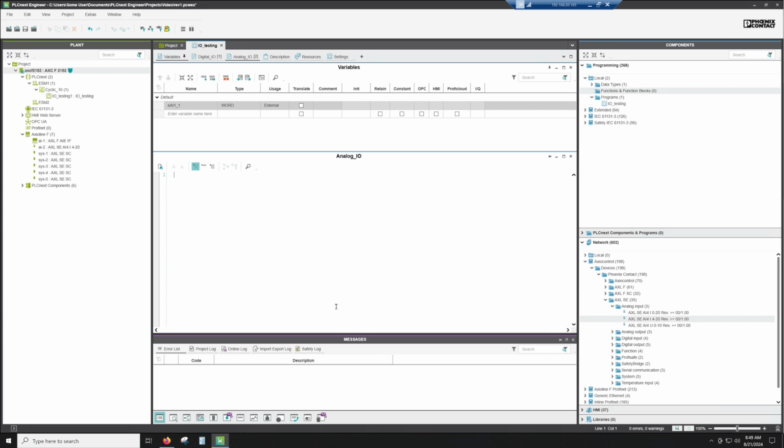All right, so today we're going to look at functions and function blocks. We're going to start with functions, and then another video will be function blocks. So a function only has one output. So for example, if I was doing some analog scaling, I would have three inputs: the raw analog input, the high scale, and the low scale. And then that would kick out one result, being the scaled analog value.